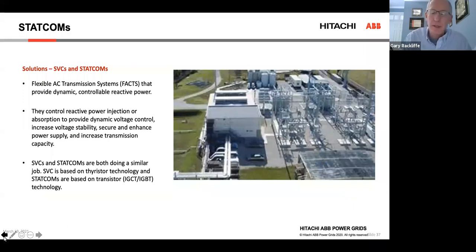So what a STATCOM does is it relaxes the transient stability limit of the line, which means by being able to inject voltage, you can move more power down a transmission line or a cable. And then the criterion is, if you lose that cable, you still need to be able to maintain the stable operation of the grid. How much power you can move down a transmission line or a cable, and still lose that line without disrupting grid operations, is called the transient stability limit. Being able to inject reactive power to support the voltage relaxes that limit, which means you can move more power down the line. The other limits for a transmission line or a cable are thermal, which is how much current you're pushing through, and then there's a physics limit, which is the difference between the two voltages. So the STATCOM enables you to move more power.